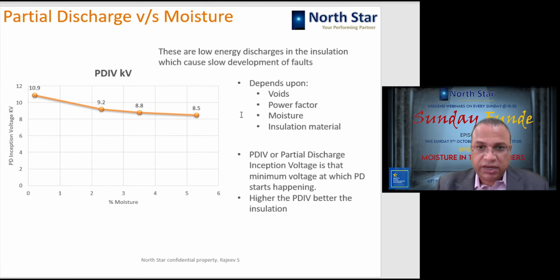So the voltage at which partial discharge starts is called the partial discharge inception voltage, or PDIV. Okay. So PDIV, as you can see from this particular graph, when the moisture content is say around 5.5%, at 8.5 kV itself the partial discharge will start. When the transformer is dry, less than 1%, then even at 11 kV partial discharge will not happen.